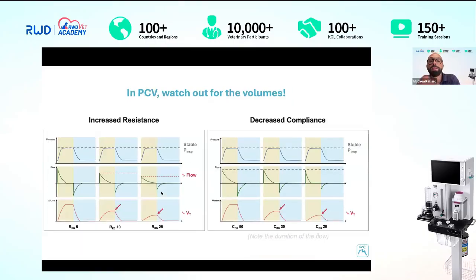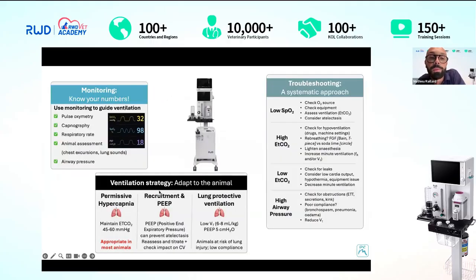In that case, when I set a pressure control ventilation, what I will have to watch out for are the volumes. If my compliance decreases or my resistance increases, you will be able to accommodate less gas to get to the same pressure. And therefore, in both cases, you will have a stable inspiratory pressure because that's your setting. But what you will end up having is less and less flow as compliance decreases or resistance increases. And you will end up having a very low tidal volume, which is particularly problematic. So when I look at pressure control ventilation, I actually consider monitoring volumes.